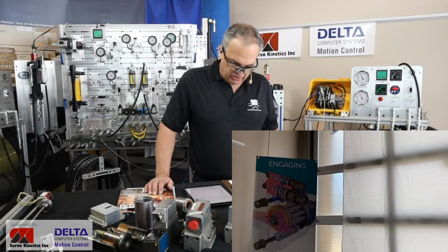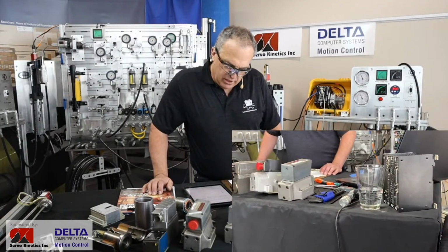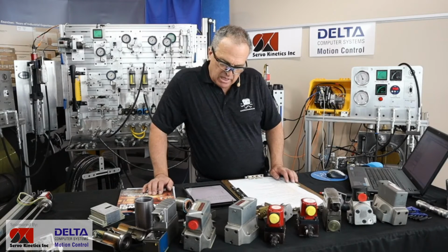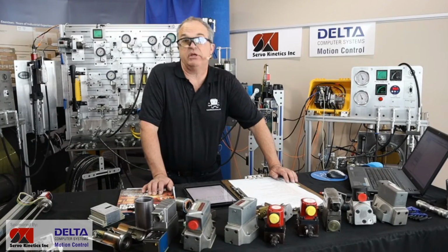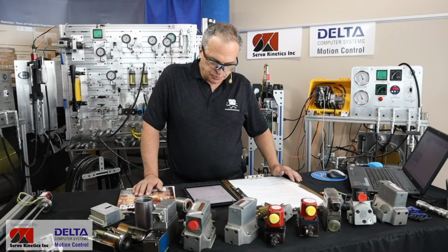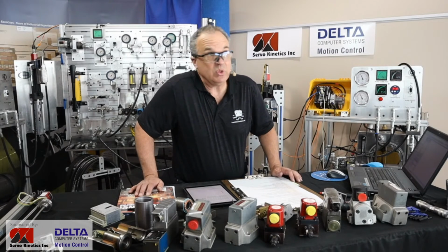Let's have a look and see if we've got any remaining questions here. Hayuza wrote in saying broken main spool spring in a pilot operated, in a proportional valve. Oh, Rexroth 4WRZ. Oh yes, I know that one. Very large, heavy proportional valve. Could it be replaced by a third-party spring? No, I don't think so.